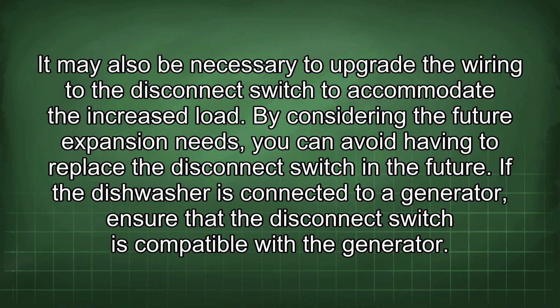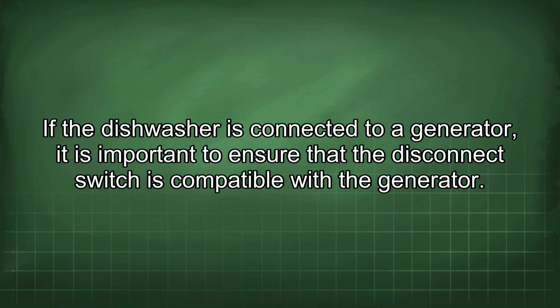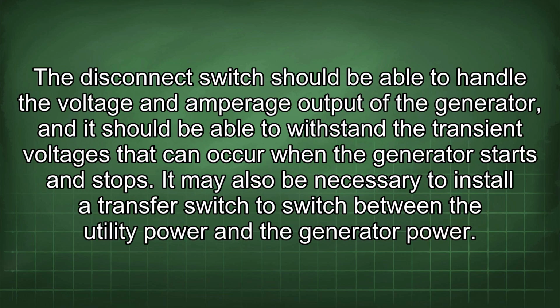If the dishwasher is connected to a generator, ensure that the disconnect switch is compatible with the generator. The disconnect switch should be able to handle the voltage and amperage output of the generator, and it should be able to withstand the transient voltages that can occur when the generator starts and stops. It may also be necessary to install a transfer switch to switch between the utility power and the generator power.